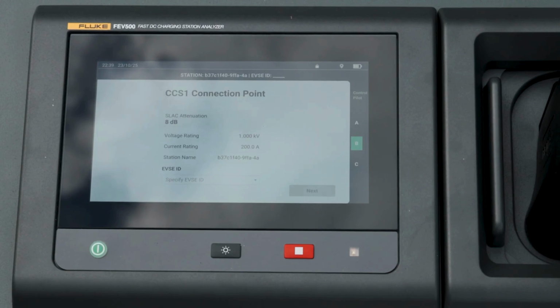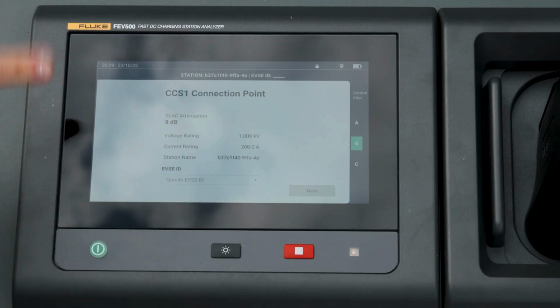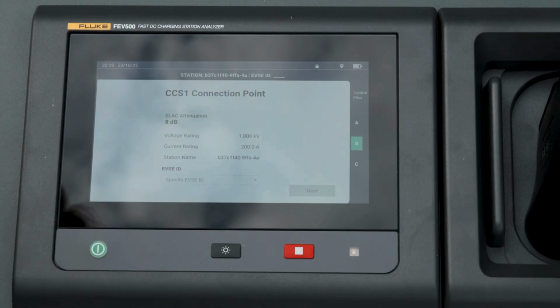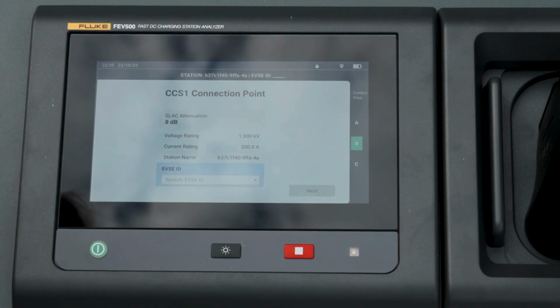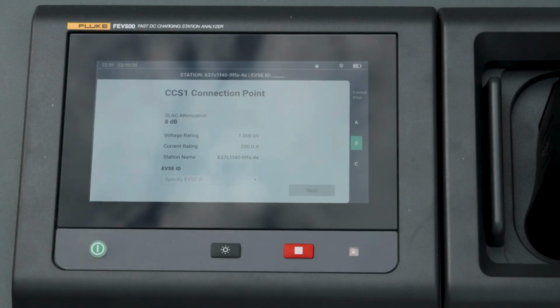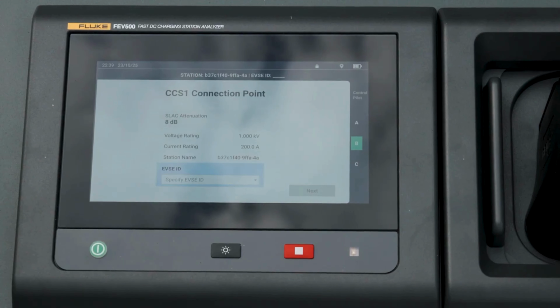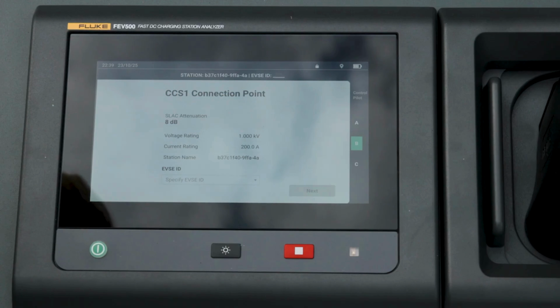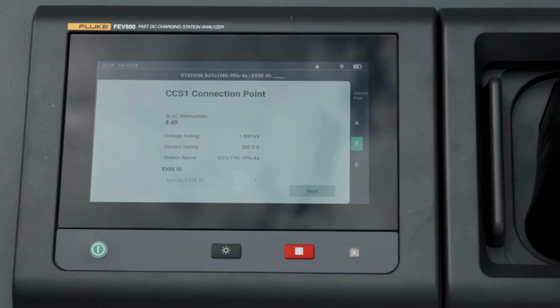Perfect, so we've got to check that communication was established. What you're seeing on screen, the first value is SLAC attenuation, a measurement in decibels. Ideally you want your measurement between 0 and 10 dB. Essentially, that's an attenuation signal that allows the charger and vehicle to identify each other to begin communicating. On the right-hand side is where low-level communication or control pilot states are listed. Later on, you'll see the low level as well as the digital or CCS charging states.